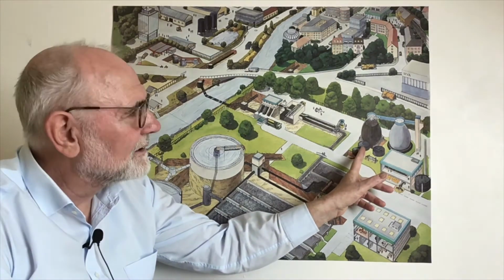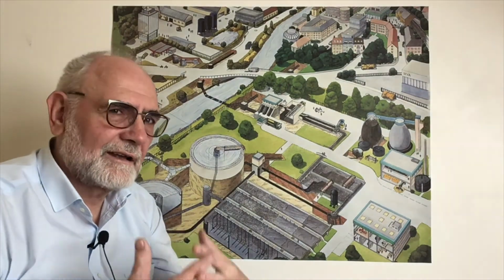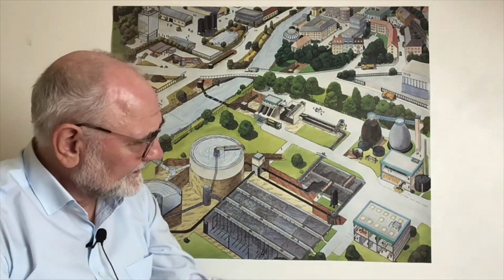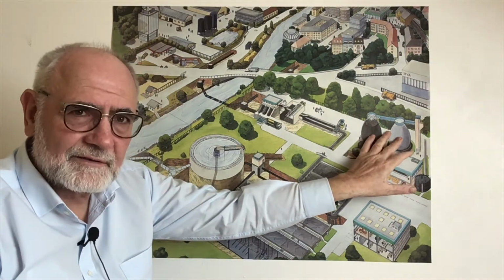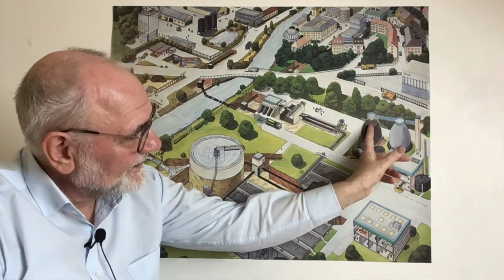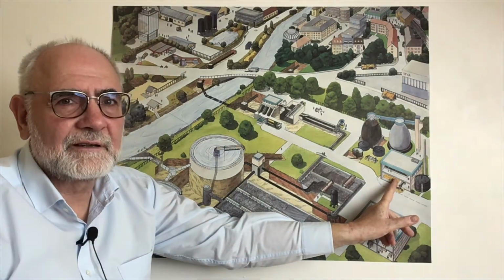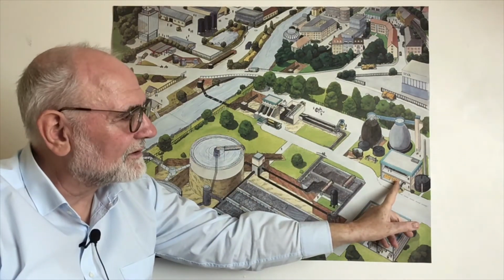That's a pre-thickener. That's a digester. Most of the wastewater treatment plants which are larger than 30,000 population equivalent in Germany have digesters. Even smaller ones now get digesters. They digest it at a temperature of 35 to 40 degrees, staying 1 month, so they produce methane gas. The gas is taken out, stored, and put to the gas engines, so they produce energy, 50, 60, 70% of the whole energy consumption you can take from this gas.